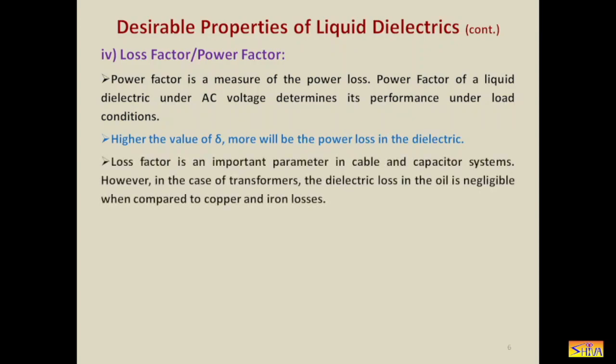Loss factor is an important parameter in cable and capacitor systems. However, in the case of transformers, the dielectric loss in the oil is negligible when compared to copper and iron losses. In a transformer, the iron losses and copper losses are there. So as compared to copper loss and iron loss, this loss factor is very, very small. Therefore, it is not considered for a transformer.